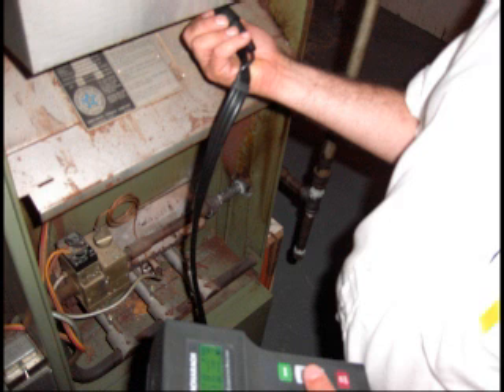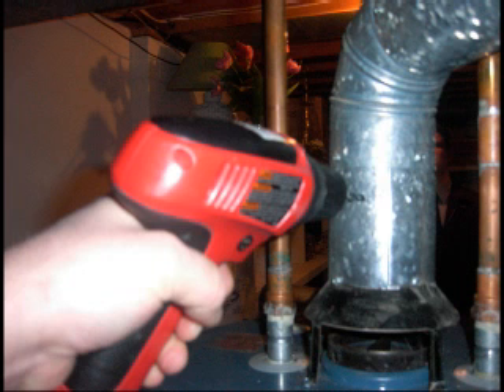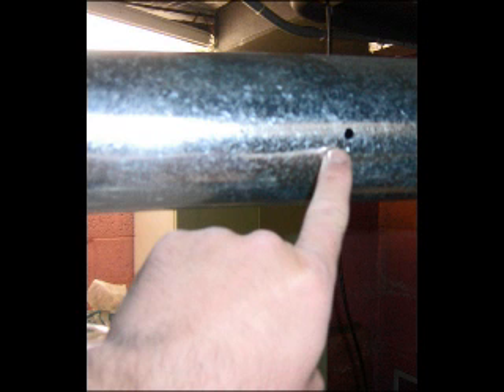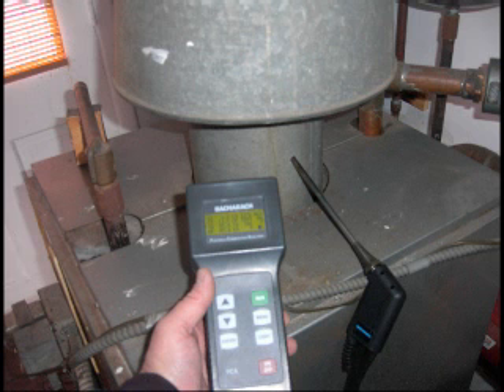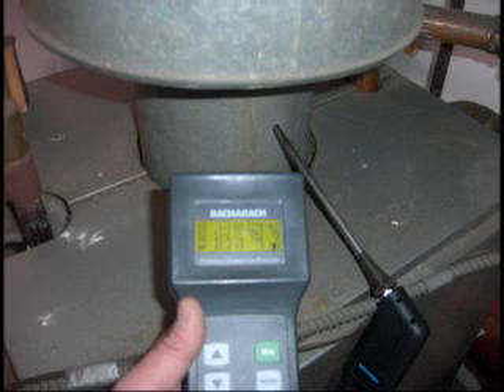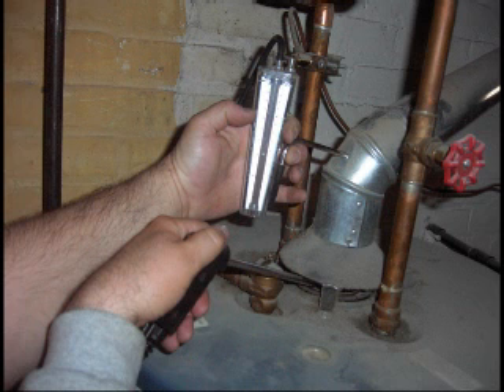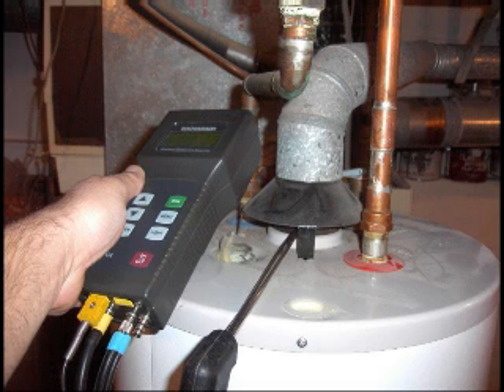When you call for your yearly inspection, cleaning, and maintenance, these guys show up with a vacuum cleaner, an oil can, maybe one or two screwdrivers, and a filter. And then they charge you between $100 and $200 and call that a furnace tune-up. Not once do they ever test for combustion or draft. If your furnace man or HVAC contractor comes to your home without a combustion analyzer or draft gauge, and they're not certified, I would probably tell them to go home.